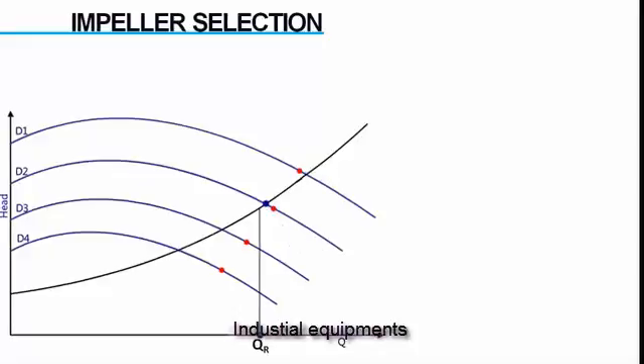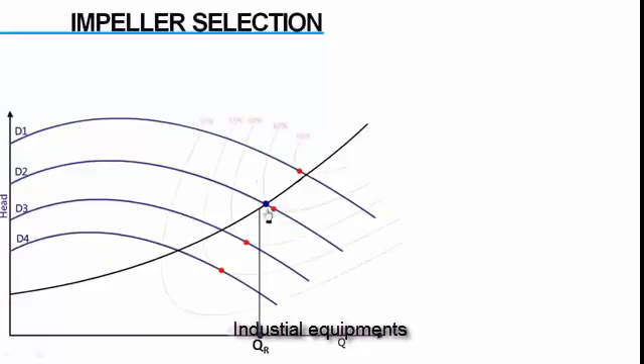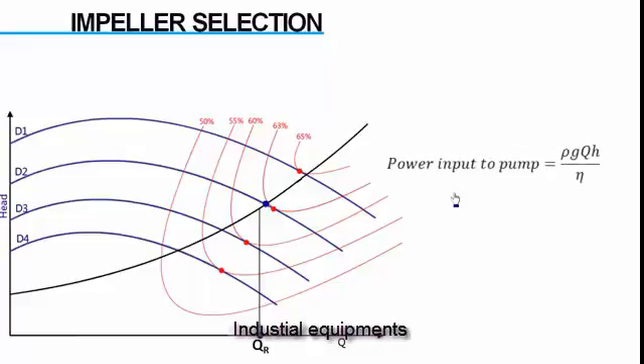In the same graph, we can represent ISO efficiency curves. So efficiency at the operating condition also can be determined. The required shaft power can be calculated using this equation. This will lead to proper motor selection.